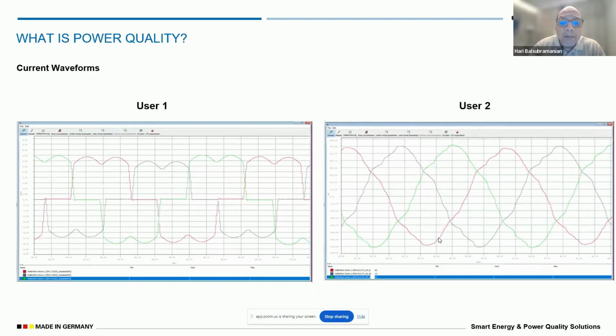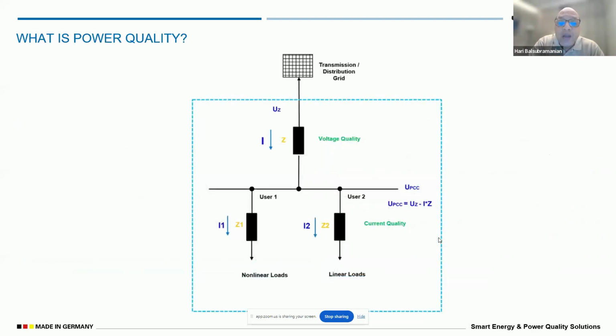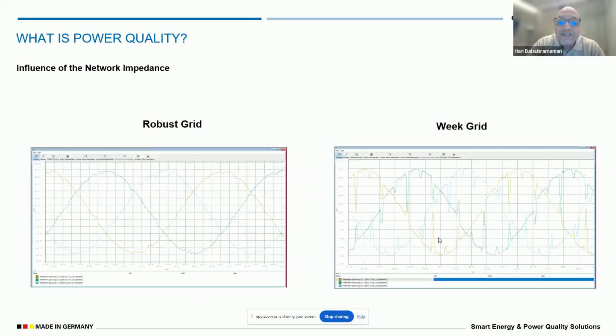So what makes the harmonics flow from one to the other? We have something called the impedance of these circuits, upstream and downstream, which can potentially have an effect on the harmonics and how they are transmitted to the other consumers. The grid is very dynamic normally. The impedance of the grid changes continuously depending on the load and the connections. In these situations, we also have the weak grid and the robust grid.